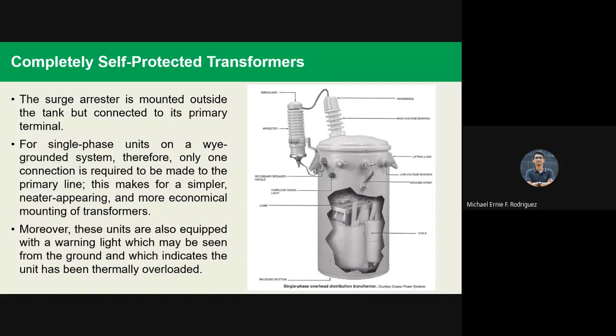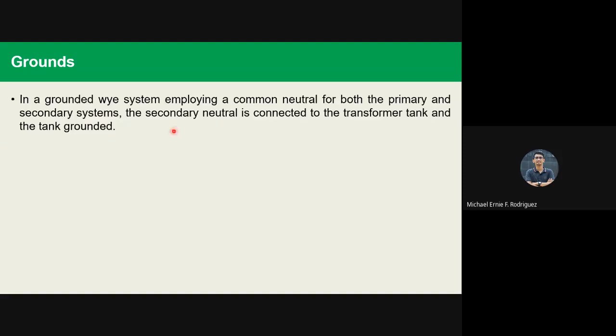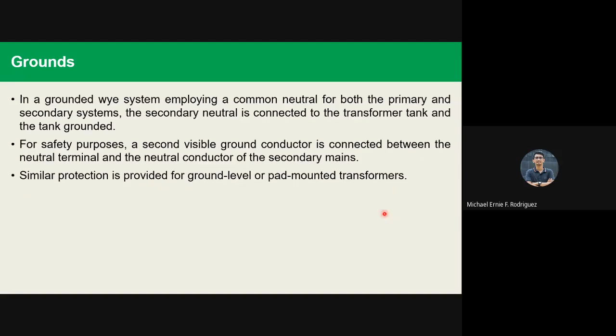And the last, ground. So sa grounding, in a grounded Y system employing a common neutral for both the primary and secondary systems, the secondary neutral is connected to the transformer tank. Okay? And the tank grounded. So yung secondary neutral connected sa tank and yung tank is grounded. And then for safety, a second visible ground conductor is connected between the neutral terminal and the neutral conductor of the secondary mains. Also, similar protection is provided for the ground, level, and pad-mounted transformers.